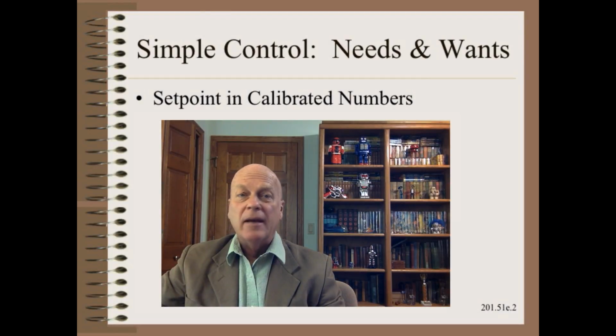Let's start by making a list of needs and wants. We absolutely need a set point. For web machines, each set point needs to be in engineering units. These units must be calibrated and calibratable per instructions in the service manual. Otherwise, reproducibility with time and between machines is compromised.